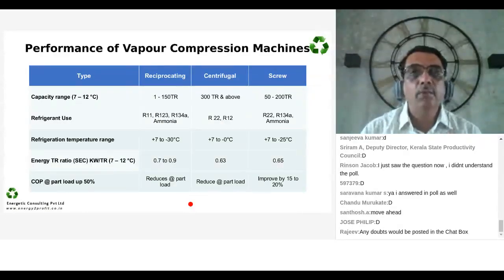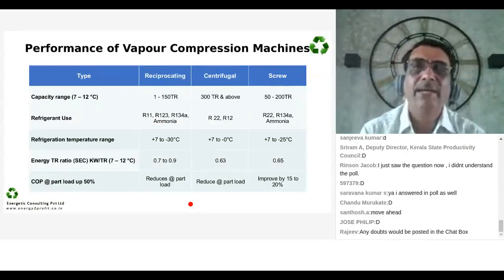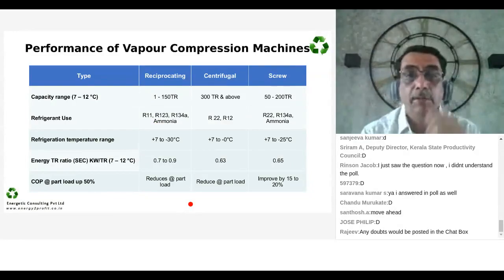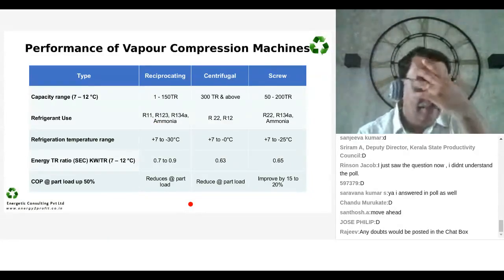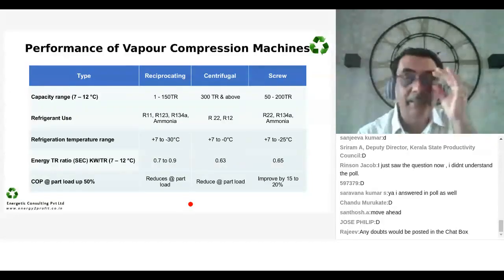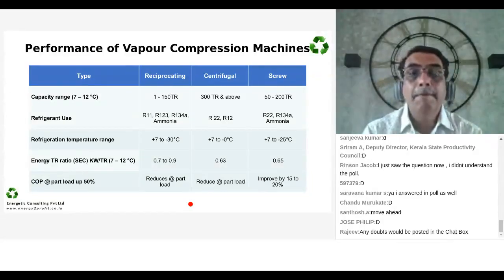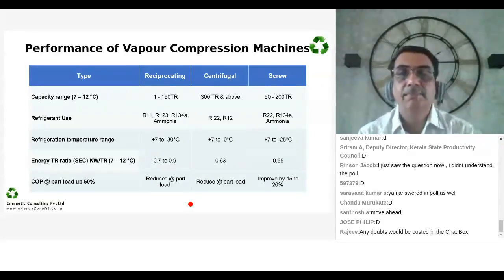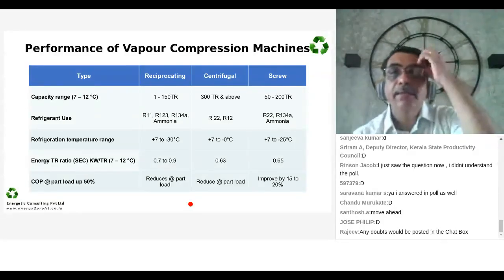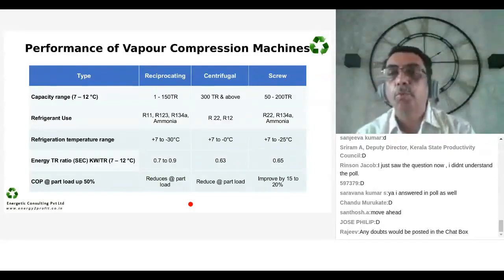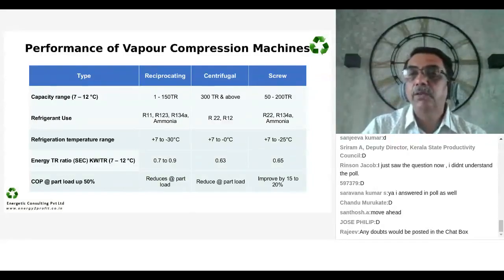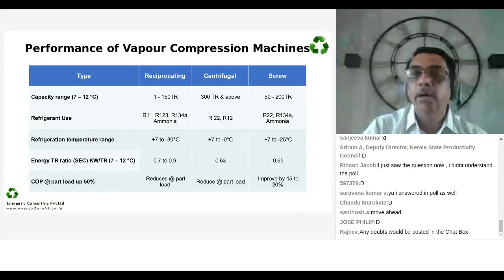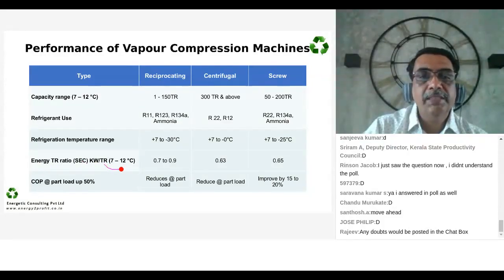Now we come to a typical range of what compressors to use. This is a very, very typical question which I confront several times as a consultant. What should be the compressor selection? Reciprocating energy wise is like 0.7 to 0.9, centrifugal 0.63 and screw 0.65. Guys, please notice, I am talking about a specific case referring to these temperatures.